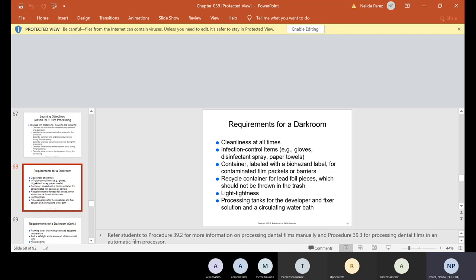Remember, you guys are putting films in little cups. Some of you are forgetting to take the cups out, throw away trash, and separate the lead foil. The films going in — the cups have to be clean, any buttons you touch inside the processor have to be clean, and any knobs outside of the processor have to be clean. Lead foil must be recycled, not thrown in the trash. The water should be changed on a daily basis. Running water with mixing valves to adjust temperature — some machines are automatically connected to water.